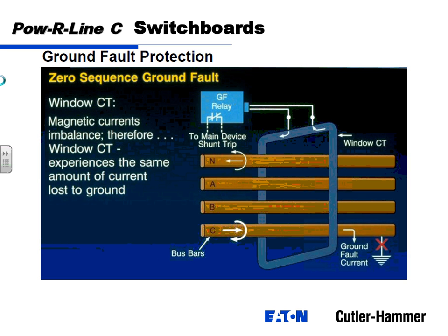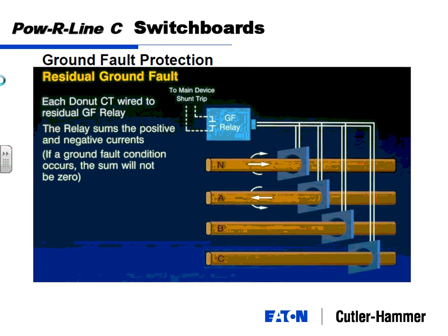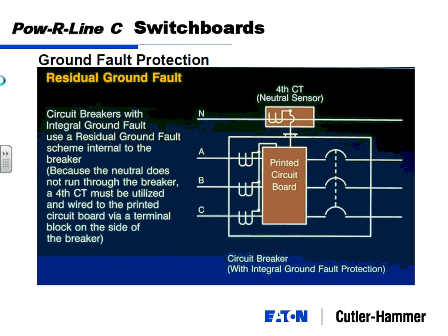If it's not 0, if you get a ground fault here, you're going to get some value measured here that is going to be equal to the ground fault current. You'll send that to a ground fault relay. Once that determines you've hit a ground fault value to trip, you'll connect to the main breaker and shunt trip the main breaker. Now, why we use this method in breakers, the residual method, which is around each individual CT, goes back to this relay. The relay is the one that sums up the vectors. And then the relay can then go to a main device shunt trip. The reason is because all that is built right into the circuit breaker.